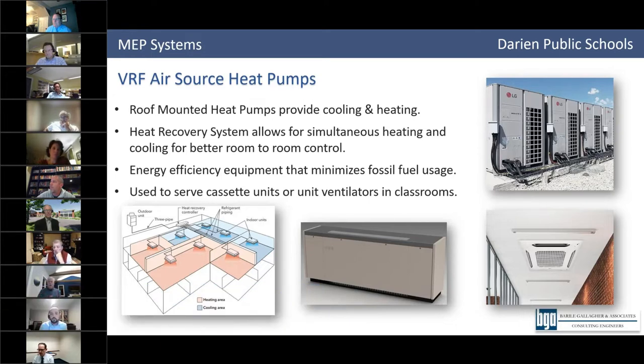Energy recovery—I think your first point is having the space to get all this into these buildings. With energy recovery, the ductwork gets really small, and one energy recovery unit can serve 10 classrooms with ductwork that's really small. If you were going to do ducted systems here, your ceiling heights would have to drop. The disruption would be considerable, plus we'd have to go floor to floor with all that.